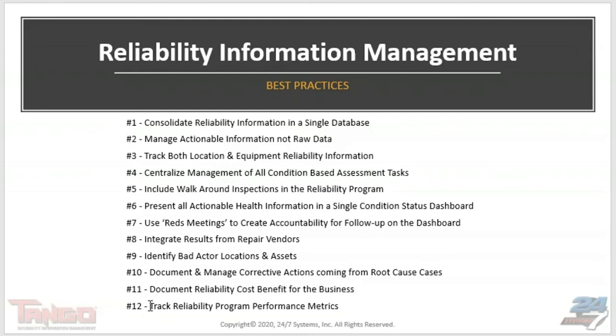Best practice number twelve: take advantage of single databasing and have a consistent means of tracking reliability performance metrics. Are you covering all expected assets on schedule, or lagging? Did you set inspection frequency goals too high? Has a manpower reduction made a previous goal non-achievable? Can you look at your MTBFs and failure mode history by equipment type and location, and determine that 90-day intervals are sufficient rather than monthly? Tracking those performance metrics is very important.